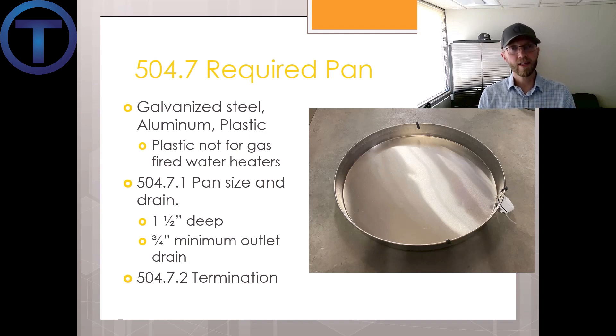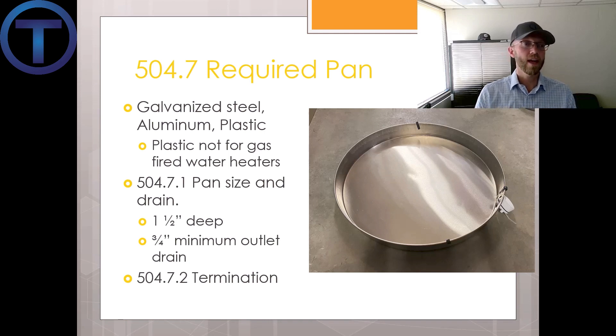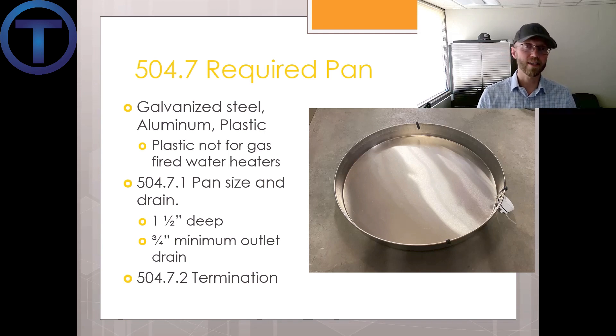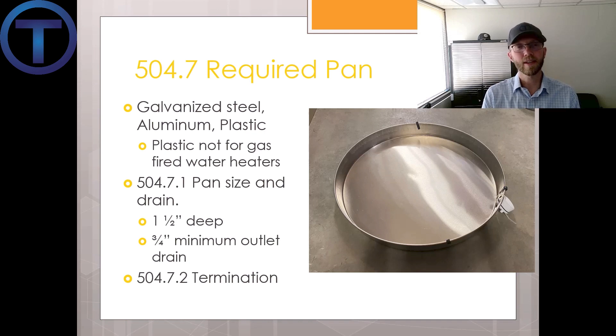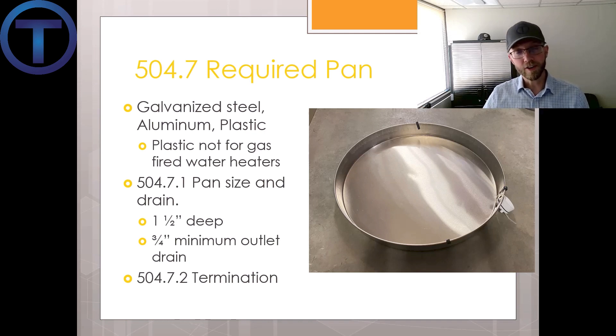Whereas if the water heater is sitting on a cement floor with a floor drain nearby, a leak is not going to damage structure — it'll make a mess but it's not unsafe. So we put a pan under anywhere we can recognize that a leak would cause damage. The pan can be made of galvanized steel, aluminum, or plastic — but plastic cannot be used under a gas-fired water heater because the gas and heat affect the plastic, making it brittle.